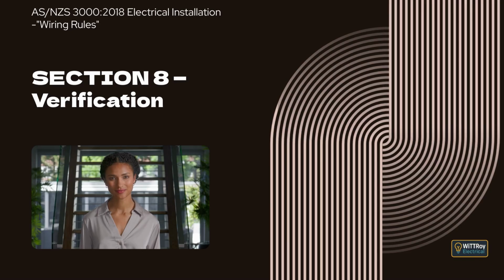Clause 8.3.3.2, Extra Low Voltage. This clause explains that testing must also be carried out on parts of electrical installations designed to operate at extra low voltage. The required tests include continuity of the earthing system for PELV circuits, insulation resistance, polarity, and correct circuit connections, all in accordance with the relevant clauses referenced.